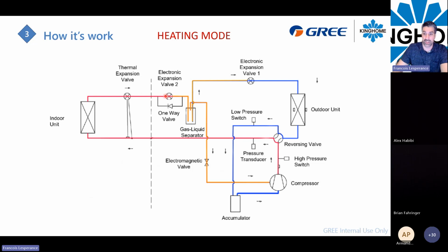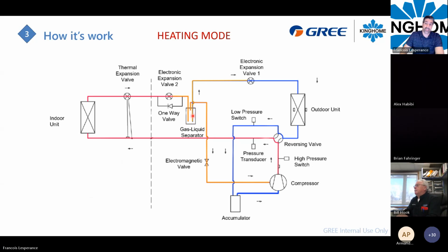It will go back to the outdoor unit, and then because here the valve is blocked in that direction, we will hit the first, it's called the EEV number 2, but we will hit that EEV, and this EEV will act just to make sure you have 100% liquid refrigerant after that EEV. So at this point we have 100% liquid refrigerant going into that gas liquid separator. This cylinder is equipped with a third pipe, right here, equipped with an electromagnetic valve.